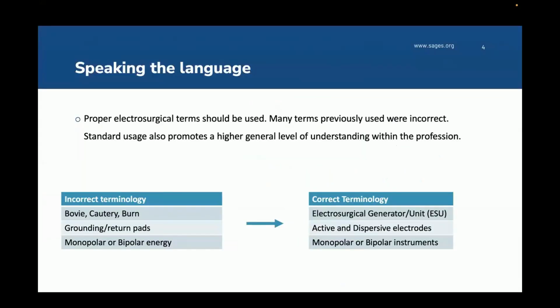So first of all, speaking the language. Oftentimes when we're referring to the terminology when it comes to electrosurgery, we use incorrect or outdated terminology to refer to some of the things that are important. So for example, Bovie: Dr. William Bovie was a great scientist, and he developed some of the earliest electrosurgery devices, but the devices that we use today are not the same ones. What we should be calling them is the electrosurgical generator unit, or ESU. Cautery: we do not cauterize during electrosurgery. Cautery is the act of heating up an instrument and then using that heat to essentially burn something else, which is not what we're doing with electrosurgery.